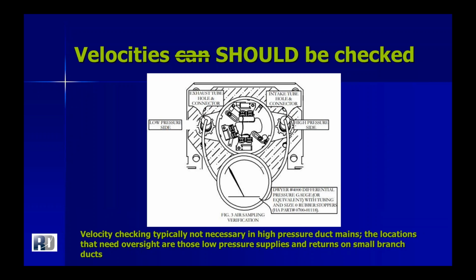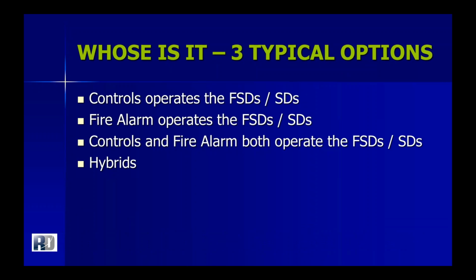Next, air velocity readings. When you read the operation and installation instructions with the minimum velocities, they should really be checked. But does our team necessarily check every single duct detector for minimum velocity? No, we do not. We pay attention to where the duct is located. If we're in a main air shaft, high pressure ductwork, we're just going to take a look at where the expected airflows are, and we would have a confidence level that we would be at adequate velocity. But if we're talking about a low pressure return duct or a transfer duct, then we would be far more concerned, and we would want to go and prove that it has the proper velocity, which is very simple to do by just putting a Magnehelic gauge across the sensing tubes.